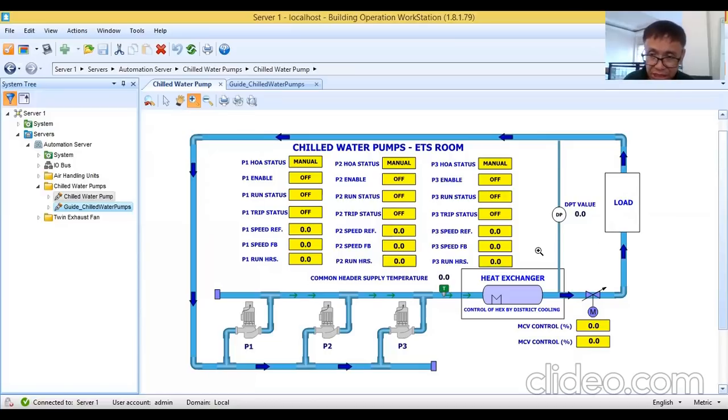So you will be needing 3 digital outputs, then you will be having 1 spare for digital output. Then for the analog output, you will be needing 3 since you are providing 4, so you have 1 spare. Now in 16 universal inputs, you will be using 9 plus 3 is 12. So you have 4 spare, so more than enough. So that will be our controller selection. Again, controller selection is 4 DO, 4 AO, then 16 universal inputs. So we are done with controller selection.